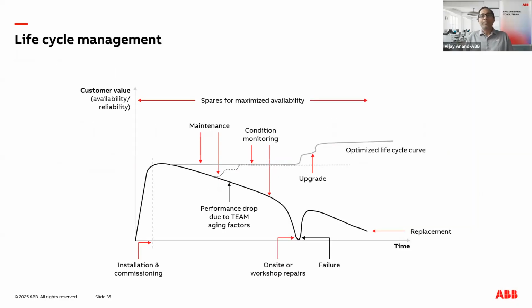This slide talks about the value a customer or a user gets from a rotating equipment like a motor, pump, or a VFD throughout its entire lifetime. The best value is typically seen when a machine is newly installed and commissioned. Subsequently, the machine is subjected to different types of stresses affecting its performance and efficiency. We in ABB call it TEAM stress: thermal, electrical, ambient, and mechanical stresses. If not properly addressed, this deterioration in the health condition will cause increase in energy cost and, worst case, lead to unexpected failure, affecting production and also increasing the downtime cost.